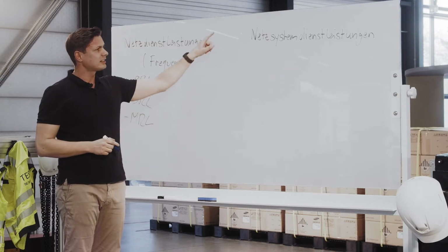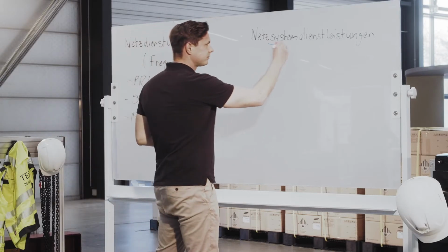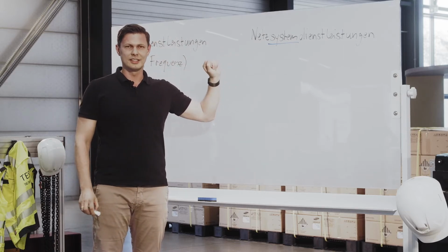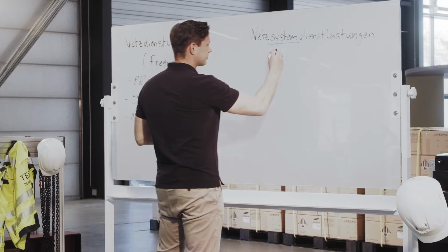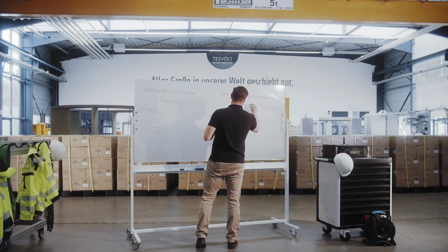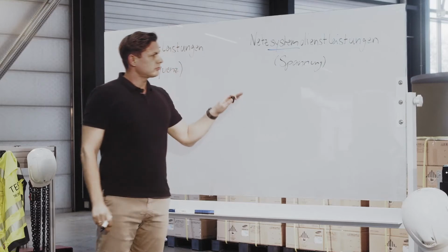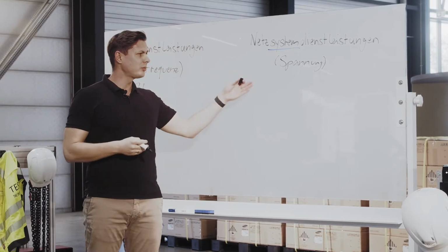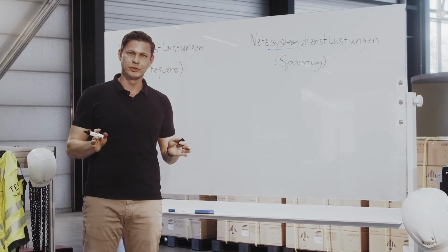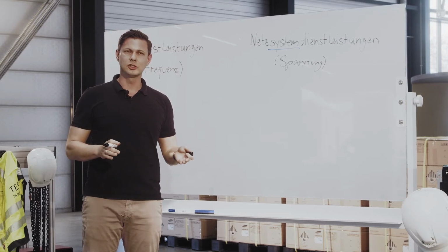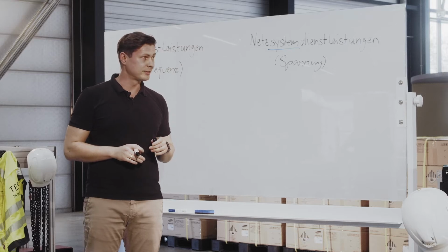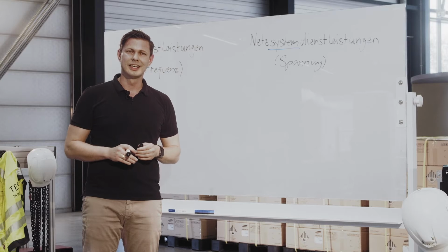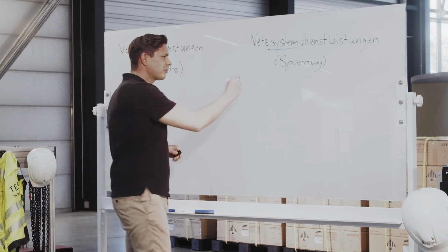These ancillary services differ from the grid system services in that the voltage is kept constant for the grid system services. The grid system services are, so to speak, the normative requirements, corresponding to the VDE-AR-N 4105 standard for low voltage, as well as the VDE-AR-N 4110 standard for medium voltage. These are the grid connection conditions. Without these, I would not be allowed to connect my generators to the grid at all.